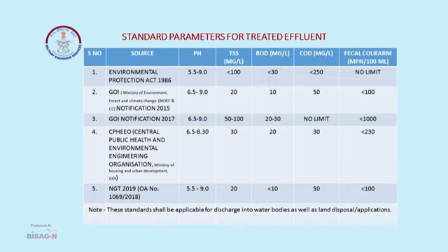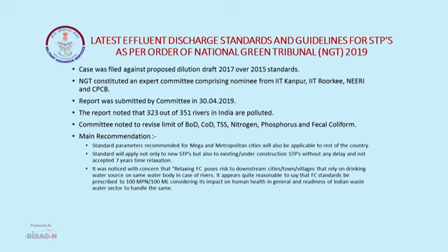With the pressure of big industrialists, the government diluted these norms by notification 2017, in which the COD limit was removed and coliform count was increased to 1000. Due to this, many NGOs and organizations filed PILs, approached the NGT, and NGT constituted a committee in which IIT Roorkee, Pollution Board, and IIT Kanpur experts were involved. NGT 2019 issued a notification which is presently applicable, restoring these limits. The main recommendation of NGT is that these standards will be applicable not only to metropolitan cities but also to villages, and no timeline will be given for existing STPs — all STPs must follow these norms.